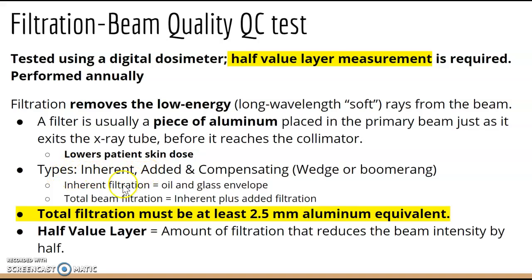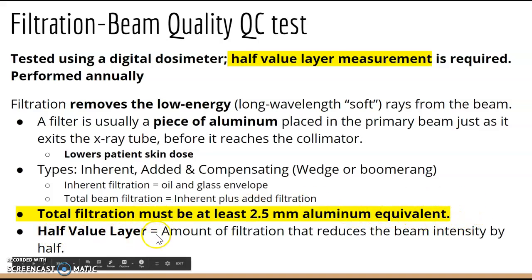Types of filtration include inherent and added. Inherent filtration is inherent to the tube — the oil and glass envelope. Added is anything added on. Total beam filtration equals inherent plus added. There are also compensating filters such as wedge or boomerang types. Total filtration must be at least 2.5 millimeters aluminum equivalent. The half value layer is the amount of filtration that reduces beam intensity by half.